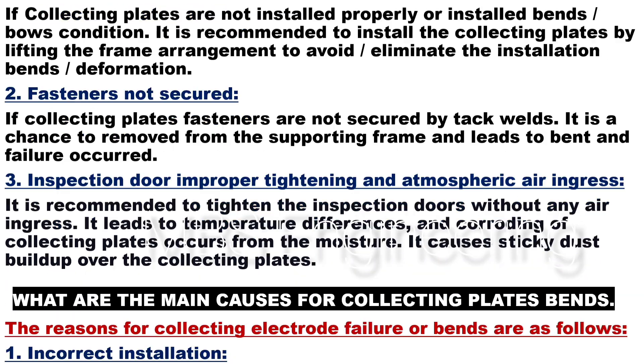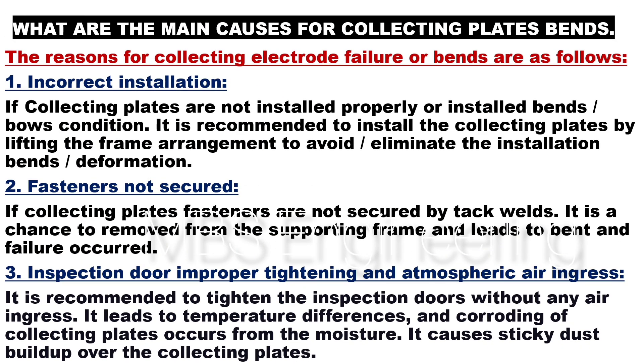One of the causes for collecting plates bends is inspection door improper tightening and atmospheric air ingress. It is recommended to tighten the inspection doors without any air ingress. It leads to temperature differences and corroding of collecting plates from moisture, causing sticky dust buildup over the collecting plates.